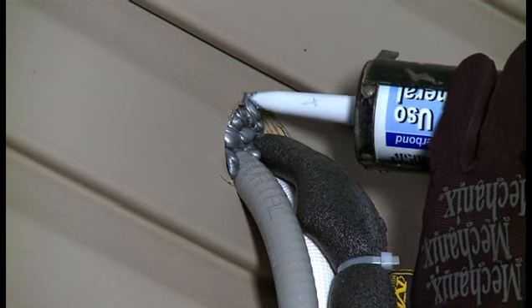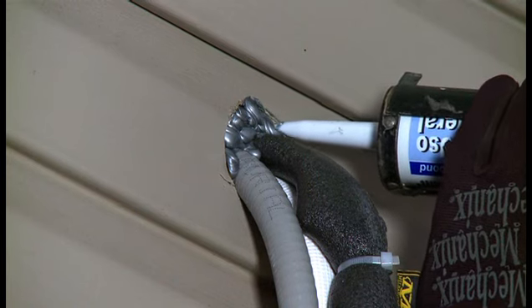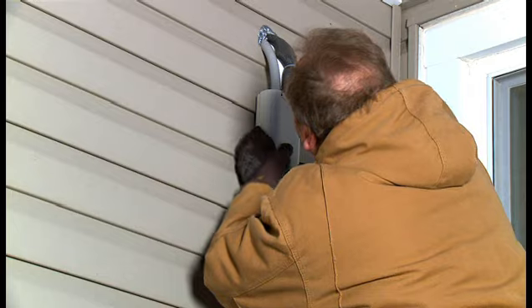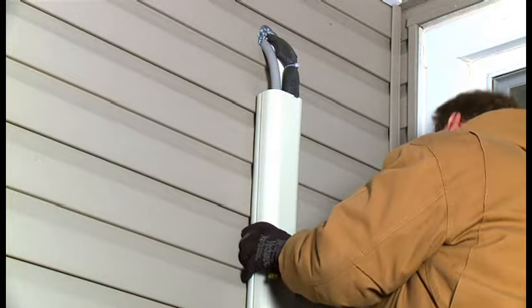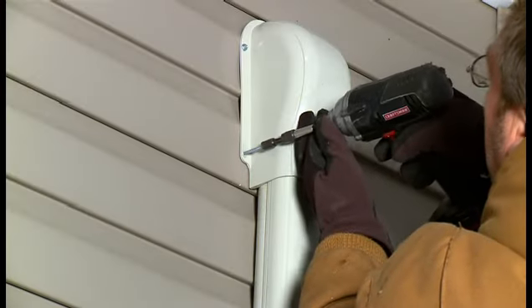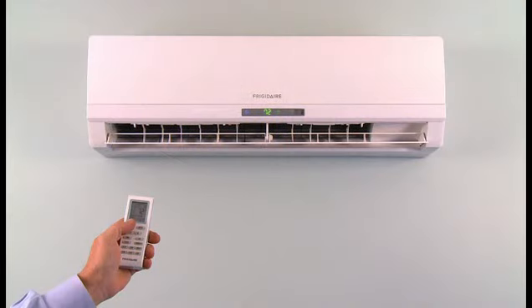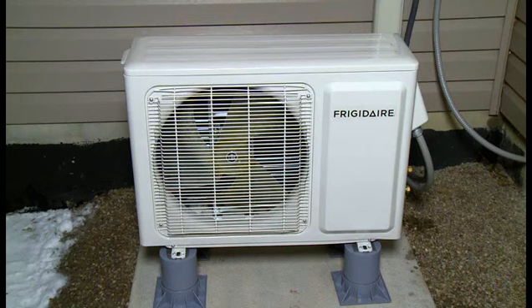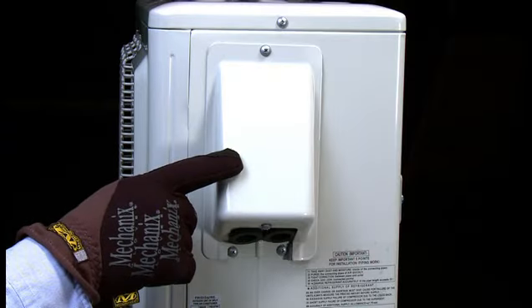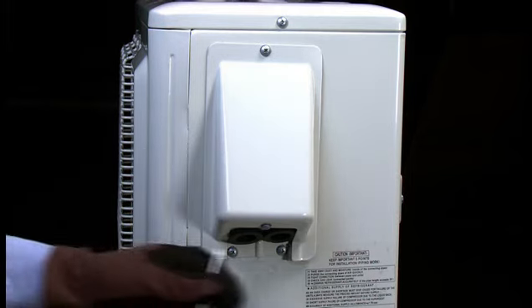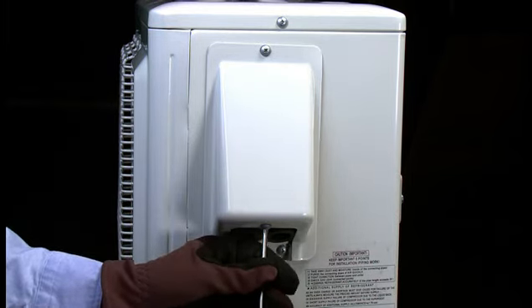Thoroughly seal the hole with a quality all-purpose interior-exterior silicone caulk. Lock the decorative line set cover into place. Attach the matching weatherhead cover. We will now complete the control wire run from the interior unit to the exterior unit and attach the power. At the side of the exterior unit, identify the electrical control board cover. With a screwdriver, remove the two screws.